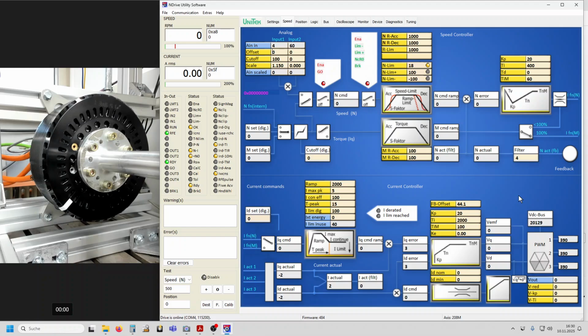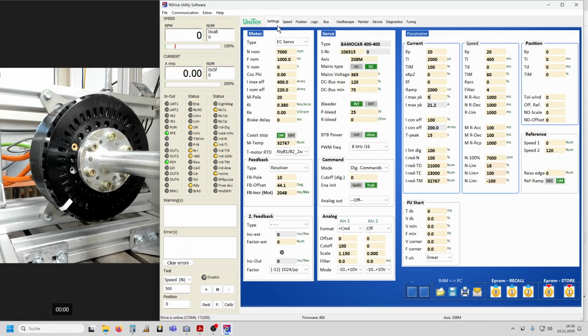So how do we do that? Basically, it's very simple. We are going to rotate the motor to roughly 1000 RPM, and then we are going to disable the inverter using the disable button, and immediately re-enable the inverter again, while having the motor control set to initialize using torque command.